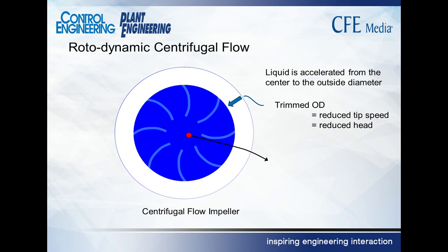When you need to adjust the flow through a centrifugal pump where there's too much flow and I need to reduce it, one way of doing that is to trim the outside diameter of the impeller. That's a very common practice with centrifugal pumps. The pump is trimmed to match the flow rate desired for the particular application. When you trim the outside diameter, you reduce the tip speed where the liquid is leaving the impeller, right at the outside diameter at the tip.